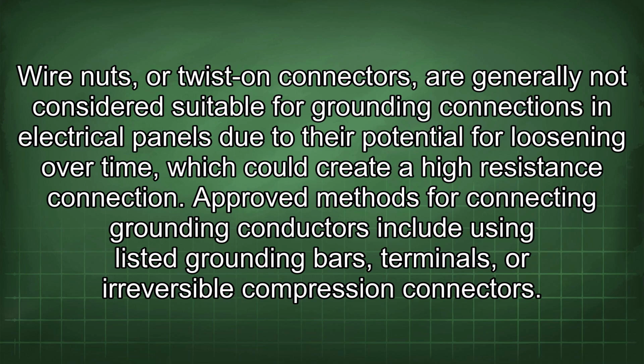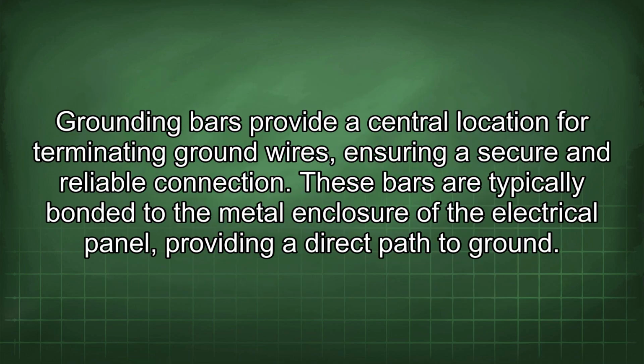Approved methods for connecting grounding conductors include using listed grounding bars, terminals, or irreversible compression connectors. Grounding bars provide a central location for terminating ground wires, ensuring a secure and reliable connection. These bars are typically bonded to the metal enclosure of the electrical panel, providing a direct path to ground.